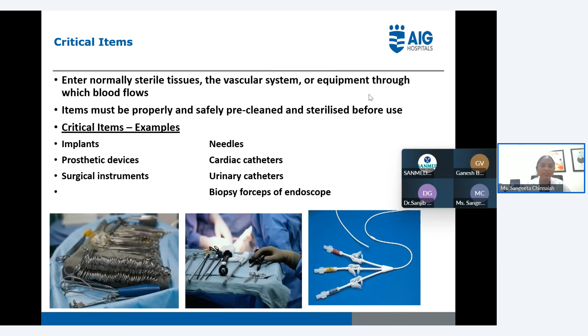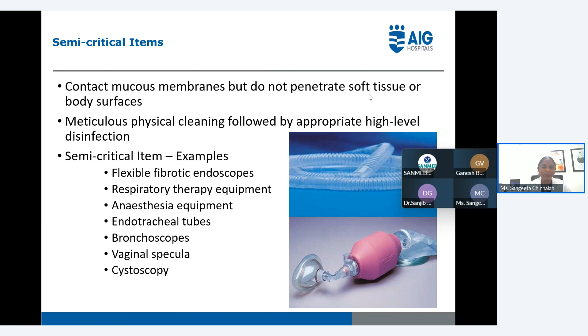Semi-critical items contact only the mucous membrane but do not penetrate soft tissue or body surfaces. They require meticulous physical cleaning followed by appropriate high-level disinfection. We can use Cidex, and second is hydrogen peroxide, H2O2, sterilization. Examples of semi-critical items: flexible fiber optic scopes, respiratory therapy equipment, anesthesia equipment, endotracheal tubes, bronchoscopes, and cystoscopes.